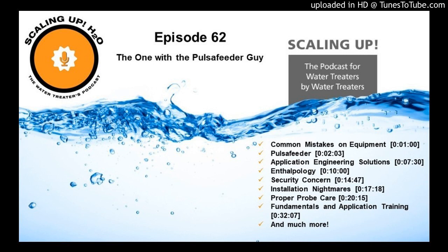When I say toroidal style, that's a probe that's taking a volumetric measurement of the process solution. The way the probe works is it emits a magnetic field in the solution. It's got an excitation emitter, and then it's got an antenna that's receiving what the reflective magnetic field is. And things that are more conductive will magnify the emitted magnetic field more. Needless to say, the probe itself is doing a volumetric measure. It's not measuring from one line to another.